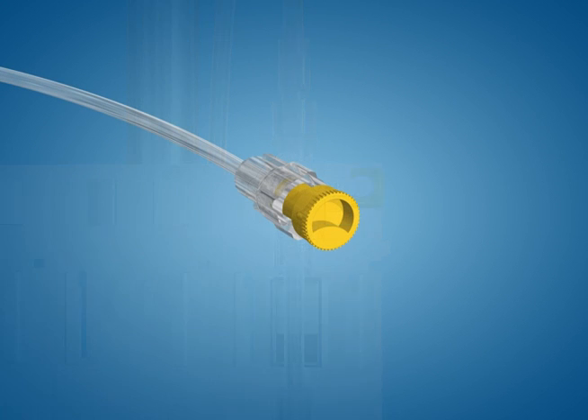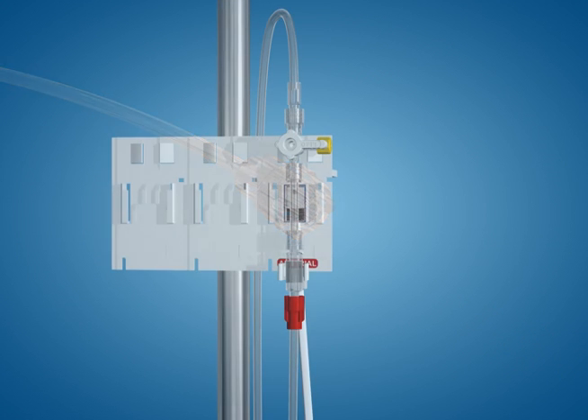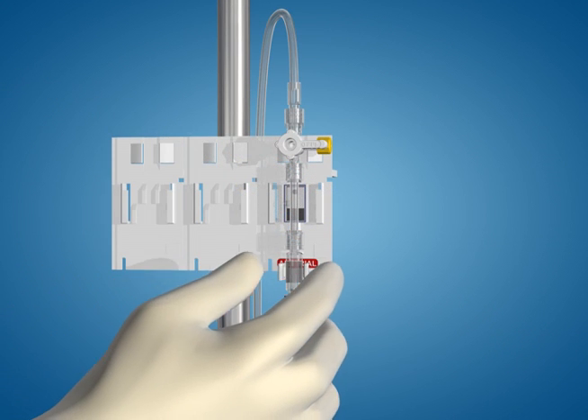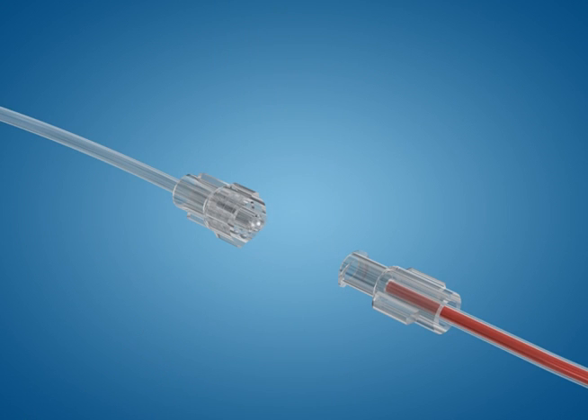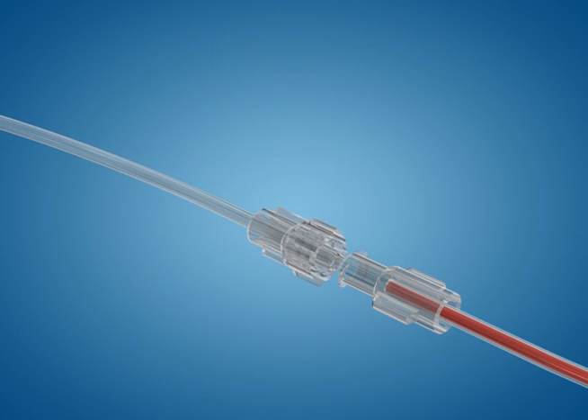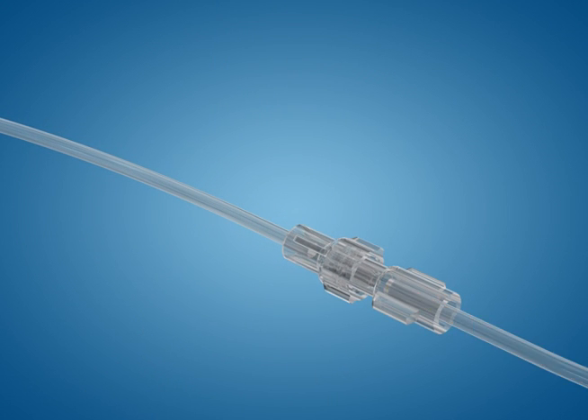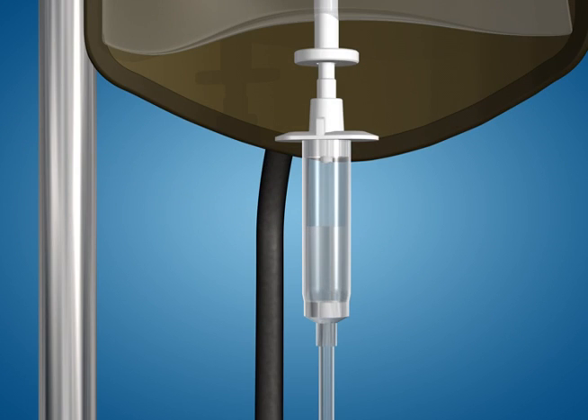You can now connect the monitoring system to the patient. Remove the non-vented cover at the patient connector. For an arterial blood pressure line, activate the flush device and allow the arterial cannula to backflow while you attach it. Then check the flow rate at the drip chamber.